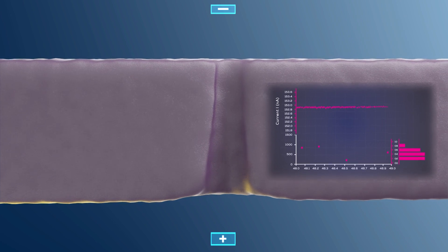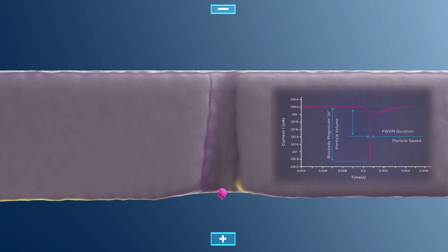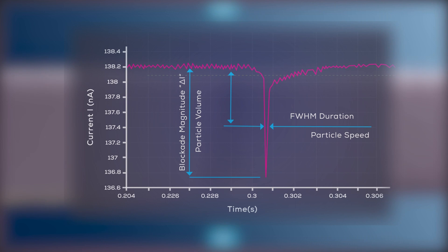Particles in the sample are driven through the nanopore by a combination of electrokinetic and hydrodynamic transport mechanisms. When a particle passes through the nanopore, conductive solution gets displaced and the resistance of the pore increases. This increase of resistance, or decrease in current, is detected as a transient pulse by the instrument. The TRPS technique is capable of measuring the size, charge, and concentration of the particles, as these properties are linked to the magnitude, duration, and frequency of the current pulses.